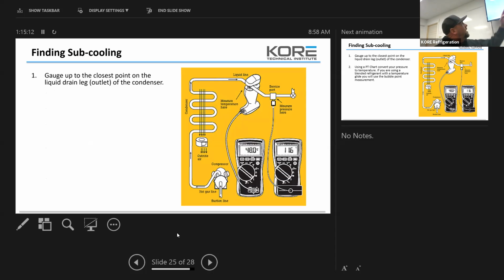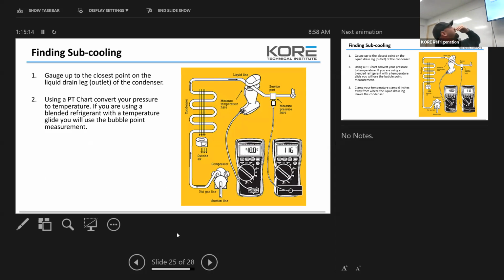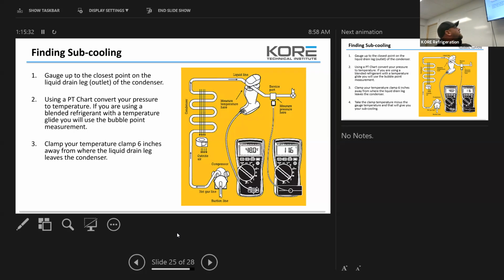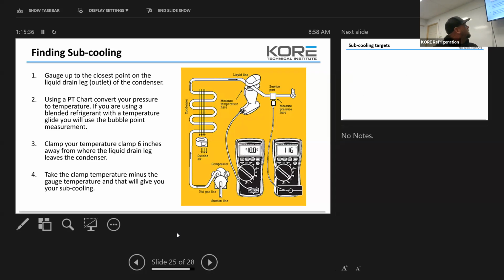Subcooling, we talked about. Gauge up to the closest point of the liquid drain leg, outlet of the condenser. Use the PT chart to convert your pressure to temperature. If you are using a blended refrigerant with temperature glide, you will use the bubble point. So remember, dew and bubble: liquid is going to be bubble, dew is going to be vapor, or saturated. Makes sense? Clamp your temperature clamp 6 inches away from where the liquid drain leg leaves the condenser. Take the clamp temperature minus the gauge temperature, and that will give you your subcooling.